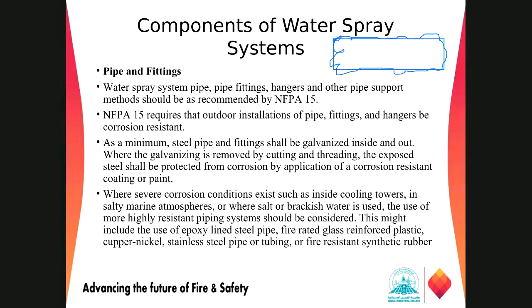Now they are talking about the case where you bought your pipe after the galvanizing unit. If for the small piping you are doing some kind of cutting at the end, maybe threading or cutting operations to put the nozzles, after the cutting we also have to apply corrosion protection at the end. For this we have corrosion resistant coatings or paint. We have to put this at those locations, because they are worried about the chances of corrosion in such piping arrangements if it is not galvanized at those locations.